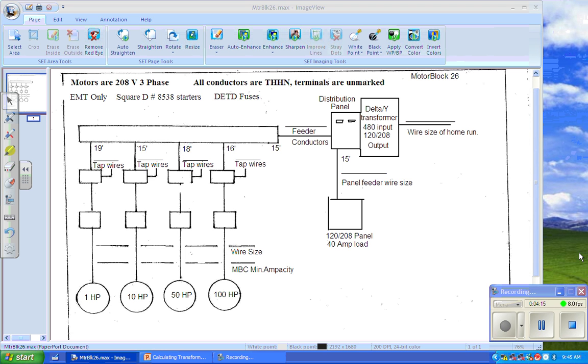And then from there on, 14, 12, and 10, we have a note, and it says go to 310.15. In other words, go to the wire table, and what is it good for otherwise? And we know what that is, so we're not going to talk about that. That's not a big deal today. Generally, that's not a good idea to have a light control circuit supplying your motor control circuit, because you're going to have signs all over the place that this control circuit is coming from someplace else and is not turned off when the disconnects in this system are turned off, right? You're going to have all these special warnings and all kinds of fun stuff.